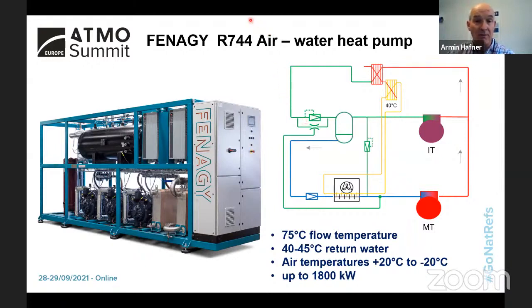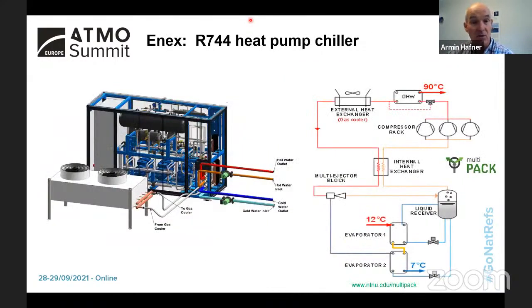So we are seeing that this is a trend to be continued also by others. And these are, in that respect, actually small systems. I know there are systems planned up to 50 megawatt with CO2 as a refrigerant, utilizing heat from the seawater, which is then heat pumped into the district heating systems. Similar concept to this, we see also that we can have CO2 heat pump chillers where we utilize both the cold and hot side, similar to what I showed you previously with the propane butane heat pump. Utilizing both sides is a clue to get the energy efficiency and implement storage where it is necessary.